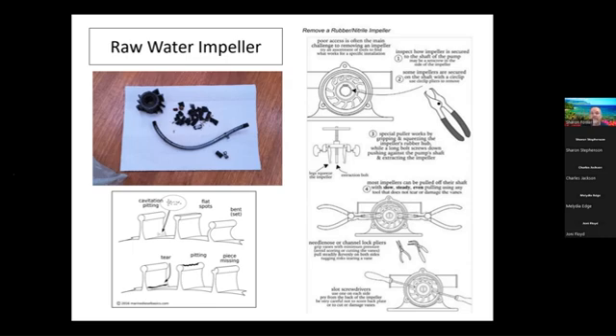A couple things you're looking for when you inspect the impeller: you want to look for flat spots, and for bent pieces that don't come straight back out when you pull it out. That happens when they sit for 4 or 5 months in one position, that's when they build up that memory and won't come back out.